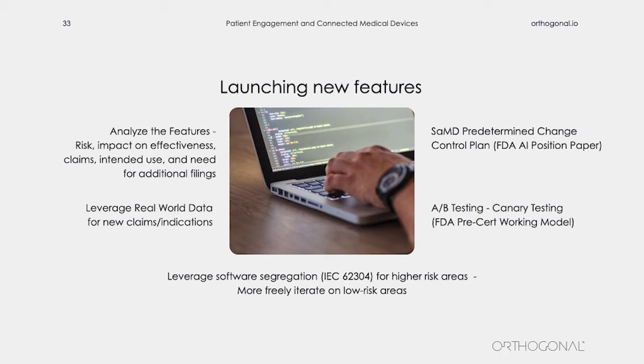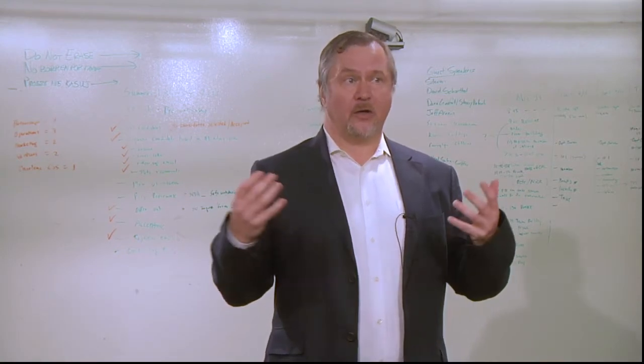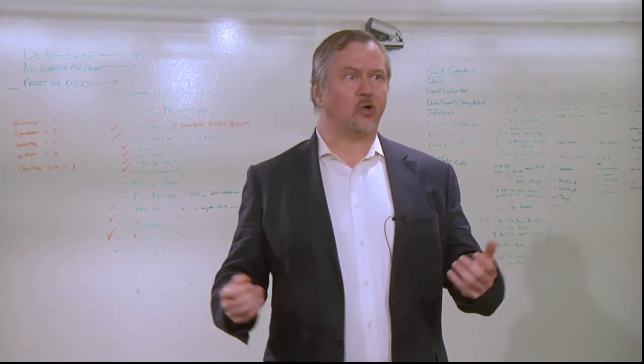When you do that, you can also leverage things like software segregation as per IEC 62304 for higher risk areas, so you can more freely iterate on low risk areas. You can also potentially use the SaMD predetermined change control plan that the FDA introduced in their recent position paper on AI in medical devices. You can leverage real world data for additional claims.